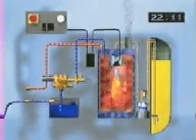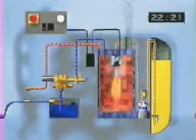And finally, the electrodes ignite this mixture. The flame burns from the top to the bottom and the resulting hot gas flows to the heating element where it heats the water. The exhaust gases are released through the chimney.